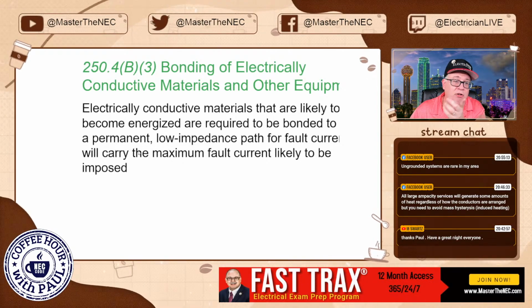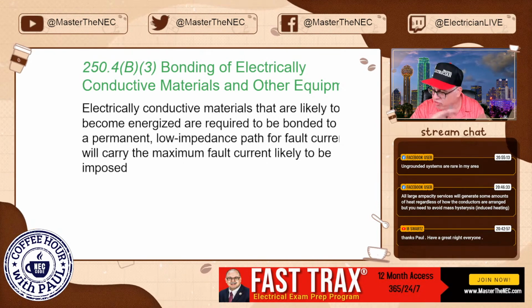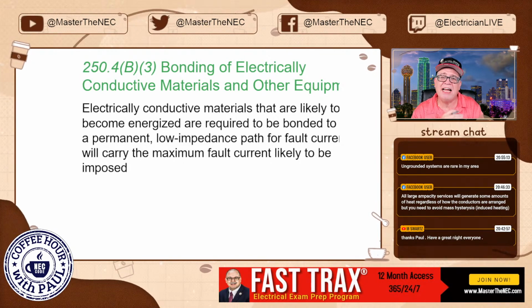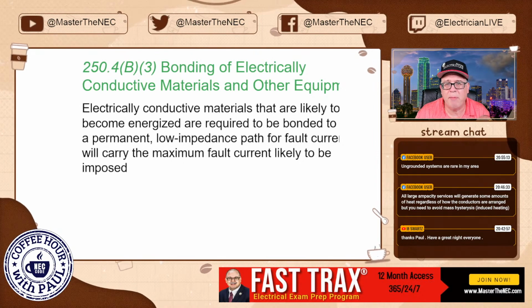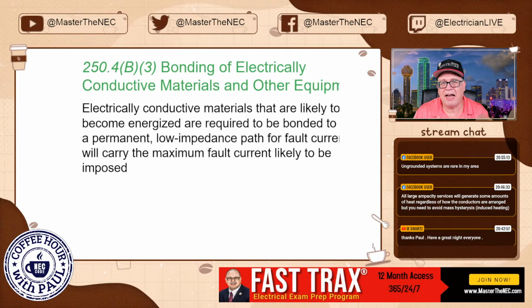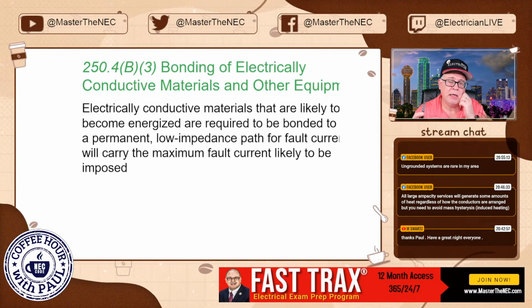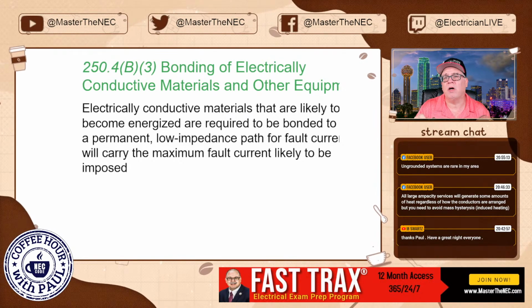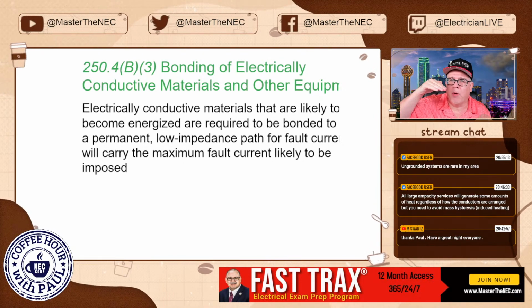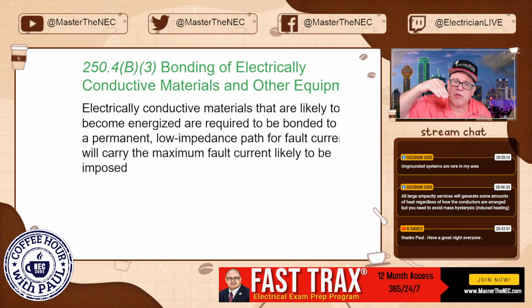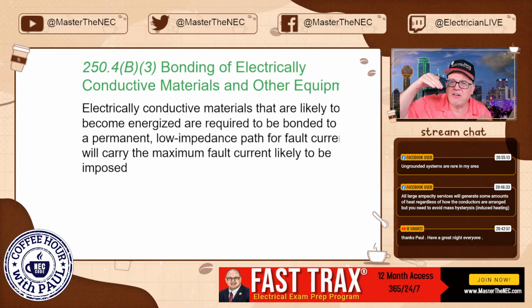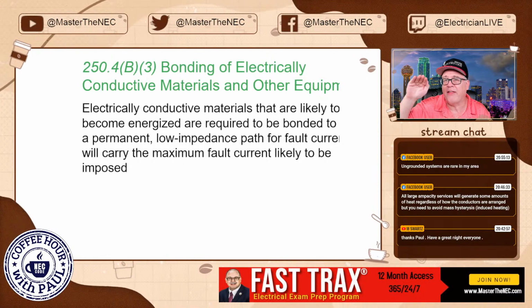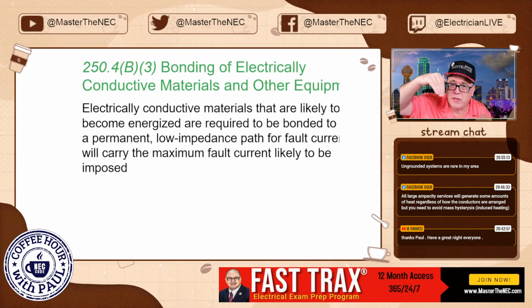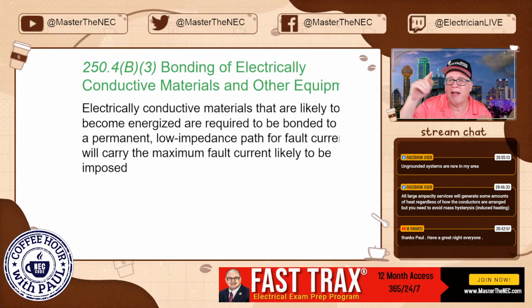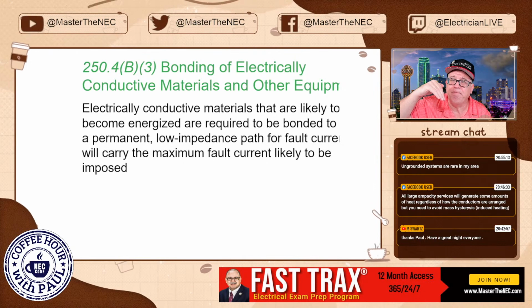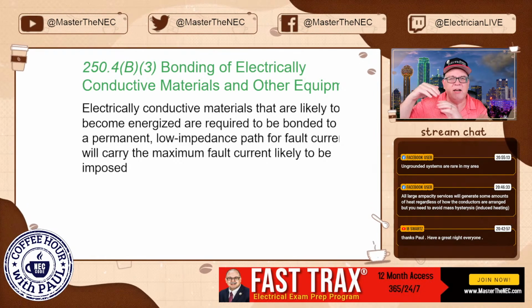Okay? Yeah, ungrounded systems, they're rare. They're still out there. They get done all the time. The only ones that I ever dealt with was in a smelting plant, where I was helping them design it as a consultant. The issue with that one was, if that thing was pouring molten metal and it was all electric, you didn't want a fault to take place and that thing to shut down in the middle of a pour. They would much rather you have one fault and let that thing finish what it's doing. And then when another phase-to-phase fault took place that completed it, then because of the heat that'll build up at that fault, it will happen.